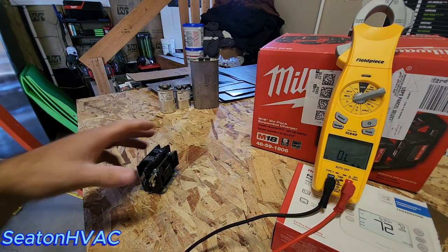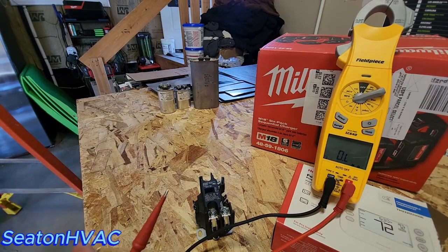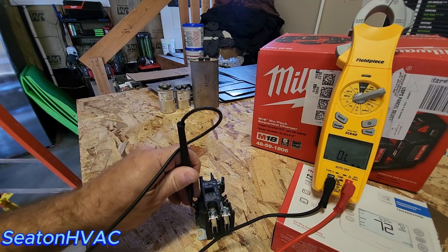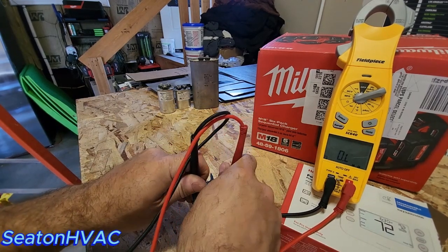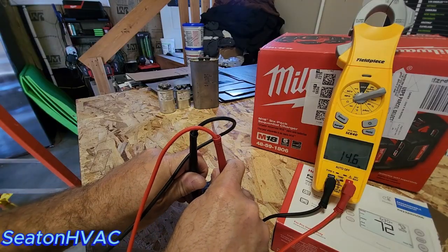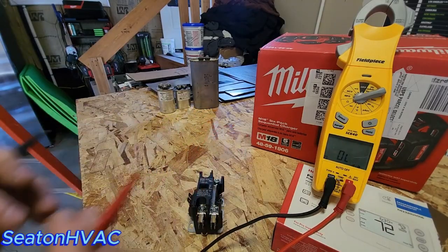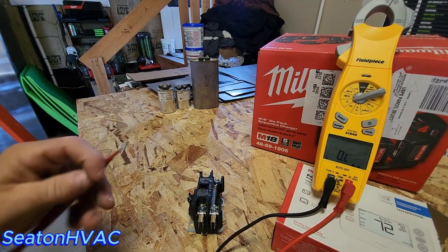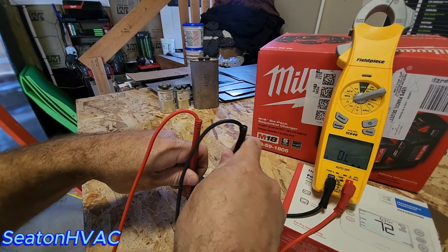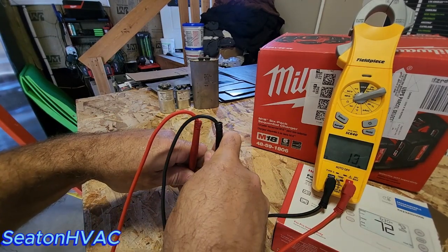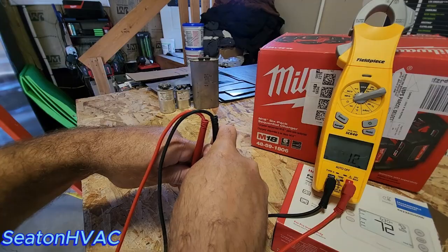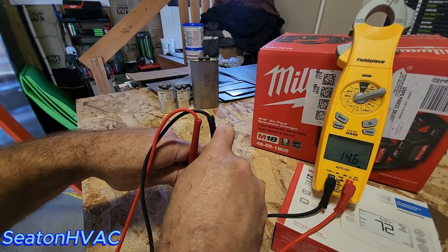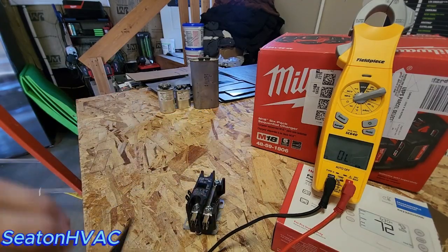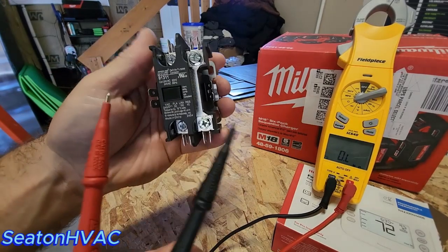So then what you're going to do is take your contactor and go from one side to the other. That's all you're going to do. And that reads 14.6. So that's good. You know, it's my rule of thumb. I know some guys are different. I've had some that are lower than 8 that were still working, but it might be a good idea to replace it. Yeah, 14.6.